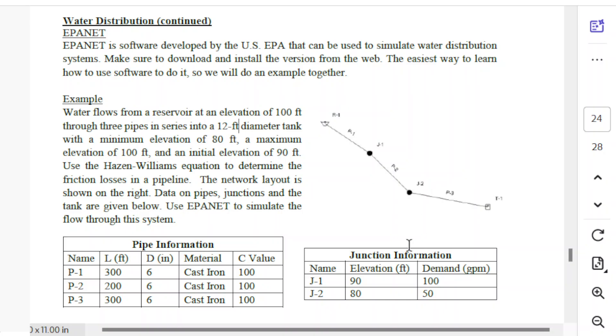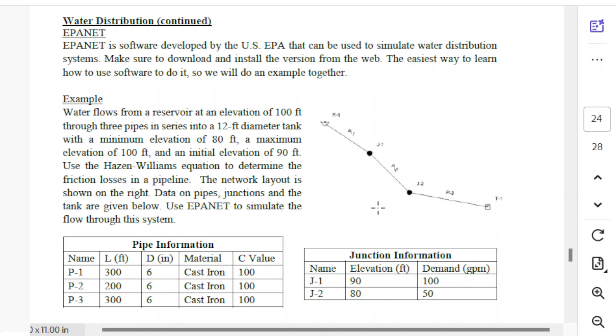In this video I want to look at how we could work this example. Water flows from a reservoir to a junction where some gets pulled out, then to another junction where more gets pulled out, and then flows to a tower that fills up. This is a pretty simple network for our first one. We're going to use the Hazen-Williams equation to calculate friction losses in each pipe, and we've got the Hazen-Williams C values, length, and diameter for the three pipes.